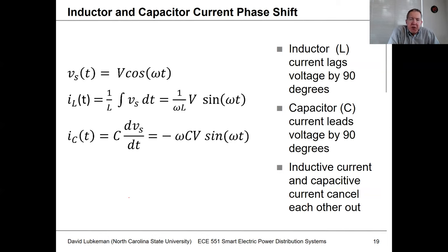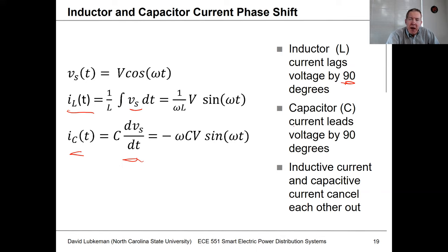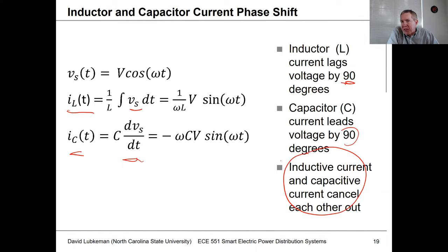Looking at the phase relationships: since inductor current is related to voltage by an integral and capacitor current by a derivative, for a sinusoidal forcing function there is a 90-degree relationship between voltage and current for each element type. Inductive current lags the voltage by 90 degrees, while capacitor current leads the voltage by 90 degrees. This creates the possibility of making these two currents cancel out, which is what capacitor applications are all about.